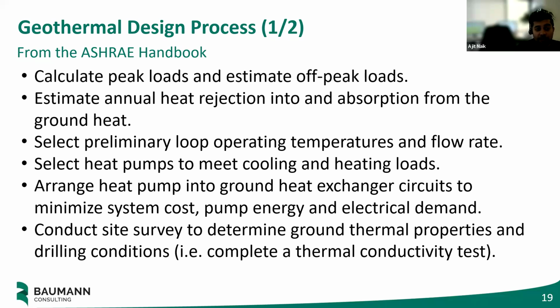Once we've got that all under control, that helps us inform not only how big of a heat pump we'll need, but how many bores we'll need, how deep they might need to be, how they'll be arrayed. Of course, some of those might be limited by design considerations. So it's kind of an optimization process where for your specific peak loads and your specific annual heating and cooling demand profiles, you select preliminary operating temperatures, flow rates, you select your heat pumps, and arrange them, lay them out.